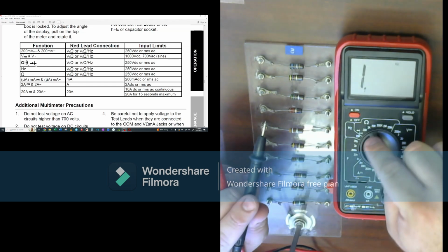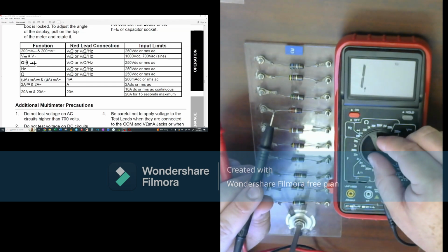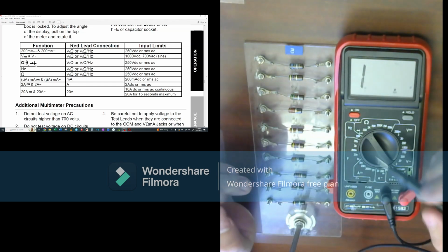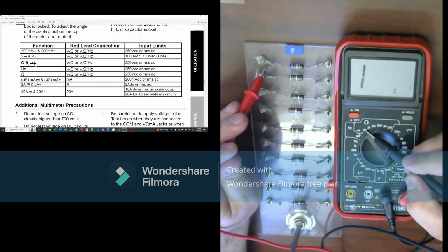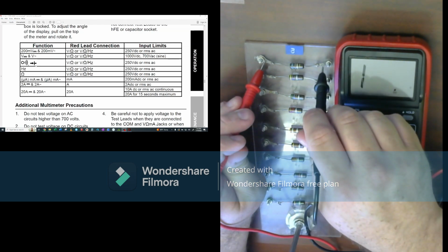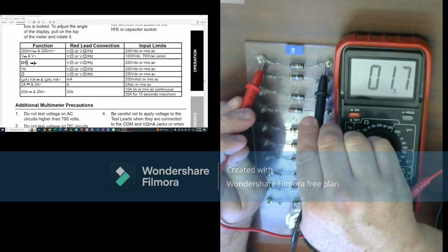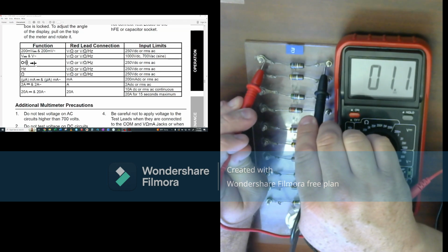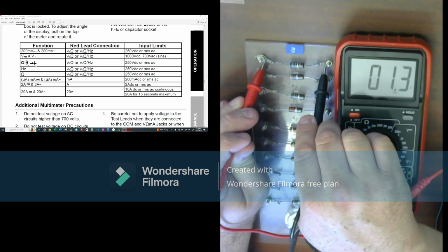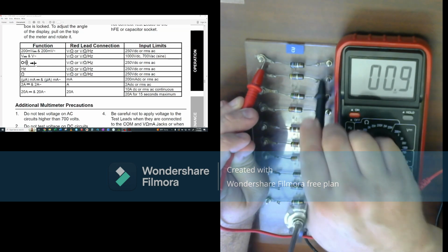So I'm on too high of a scale. I'm going to drop down to 200, so now 200 is my max. I'll measure this value again, and now it's telling me we're measuring at 1.2 ohms — very, very small, and it's going to bounce around because it's such a small value.